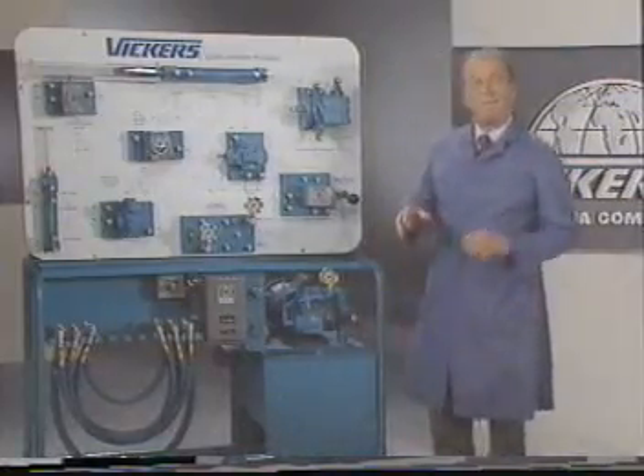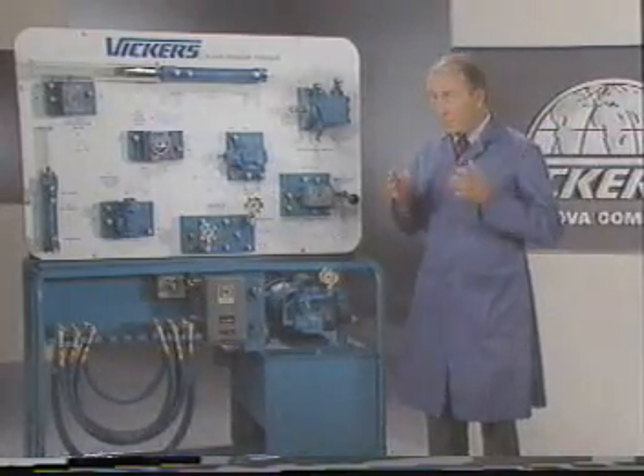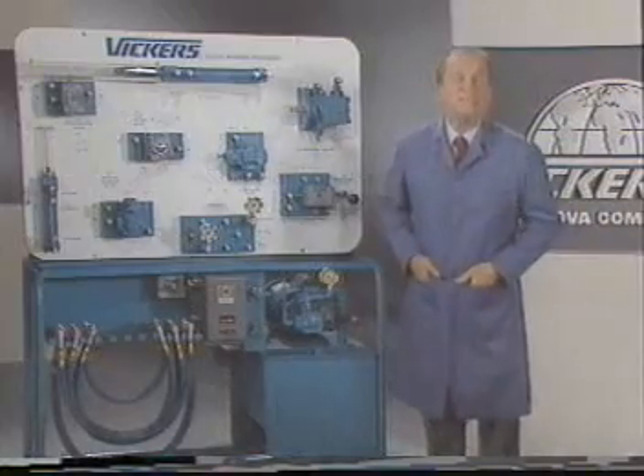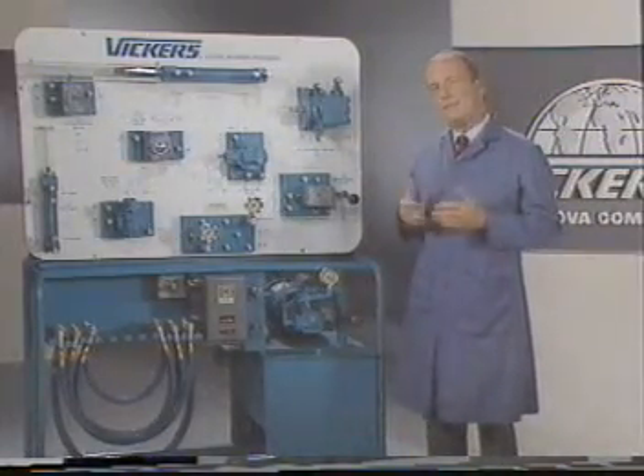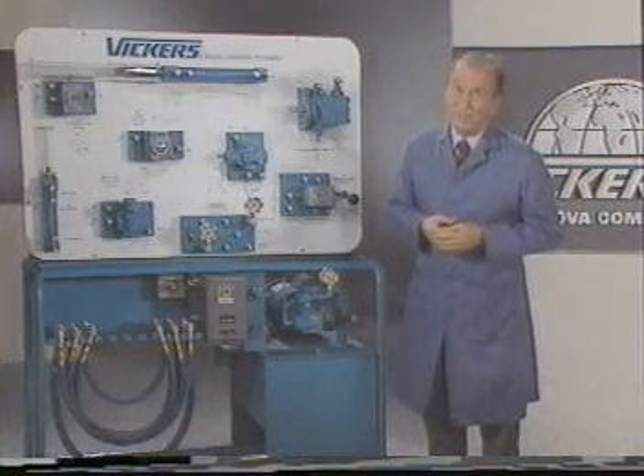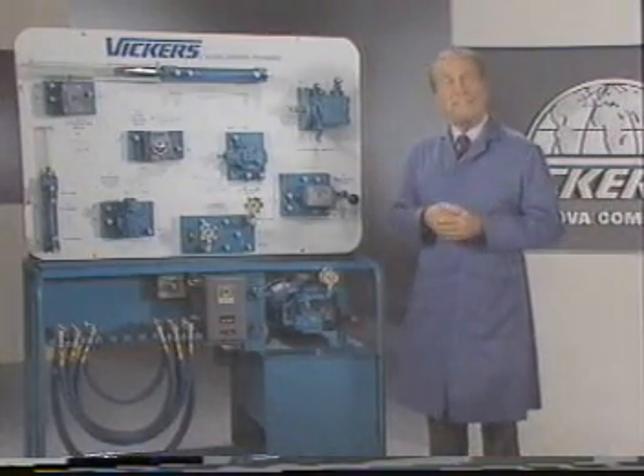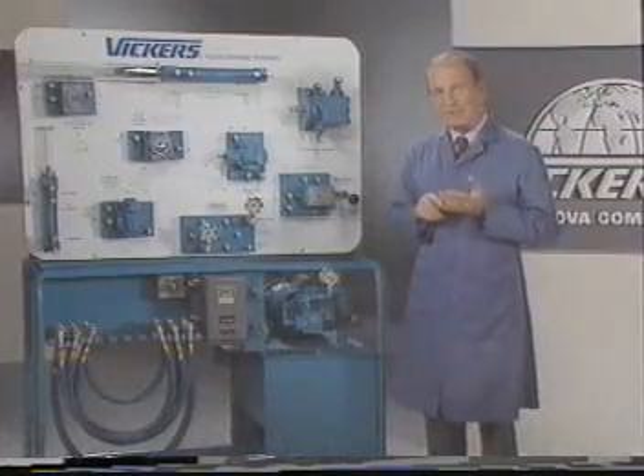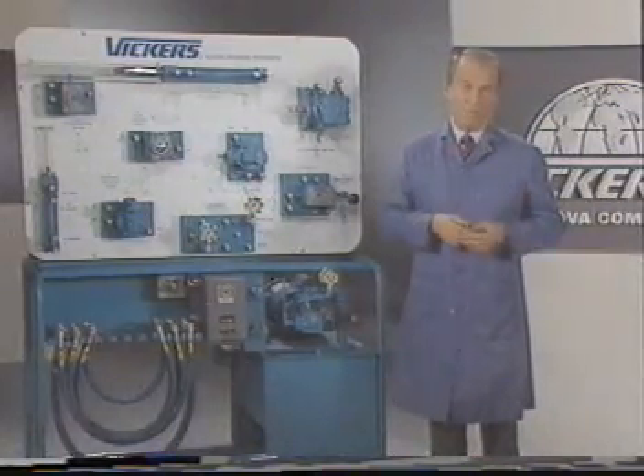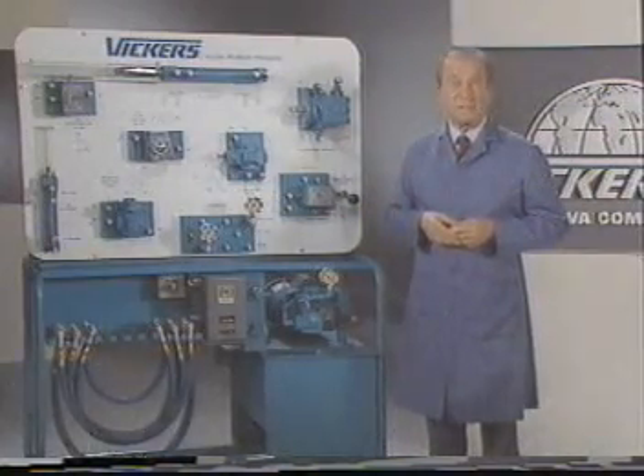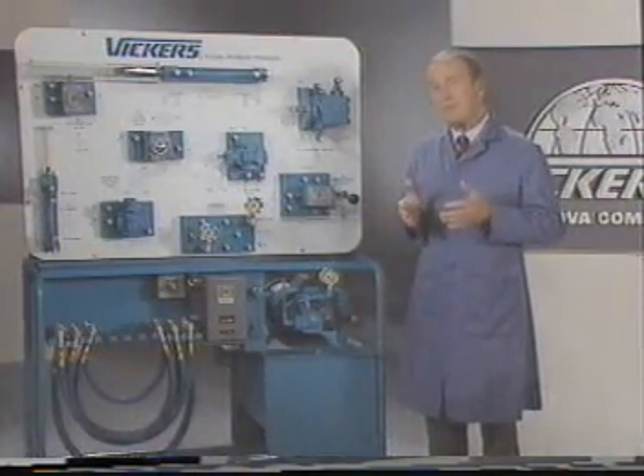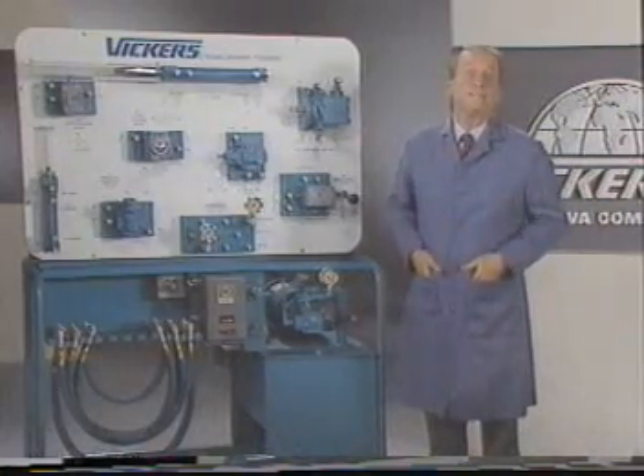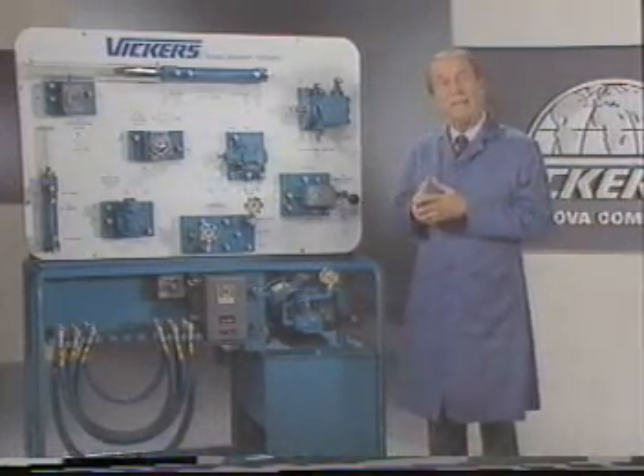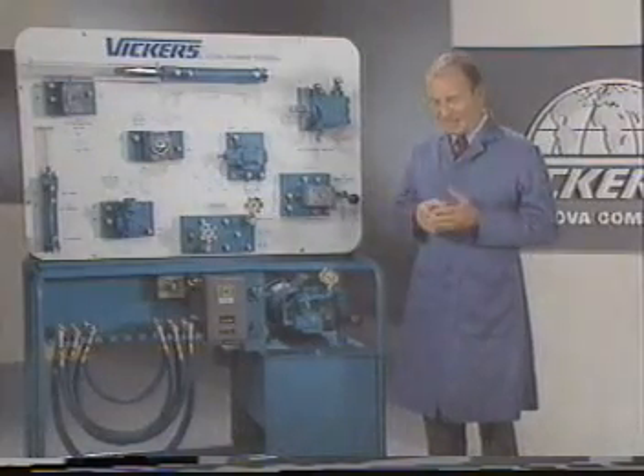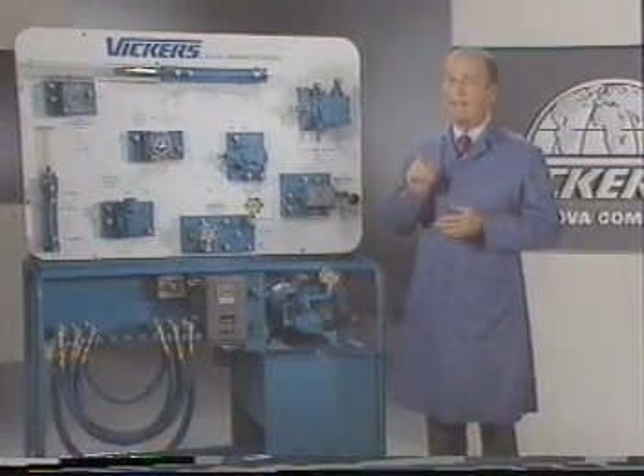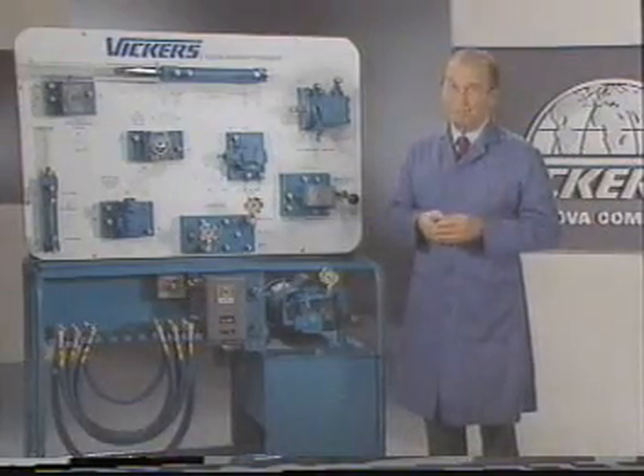Well, enough of that. Too often, people think that a pump pumps pressure. And that's not only wrong, it's downright misleading. I say that because the pump gets blamed whenever you can't build up enough pressure, and that isn't even the pump's job. All the pump is supposed to do is make the oil flow. Pressure is caused by resistance to flow. If you don't have enough pressure to do the job, it's usually because the oil has found an easier way to get back to the reservoir. Next time someone has this problem, find out where the oil is going and you'll be a hero.